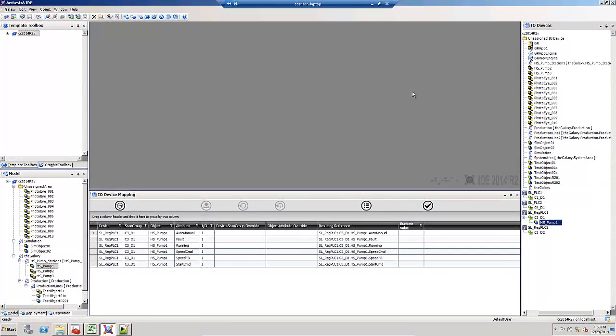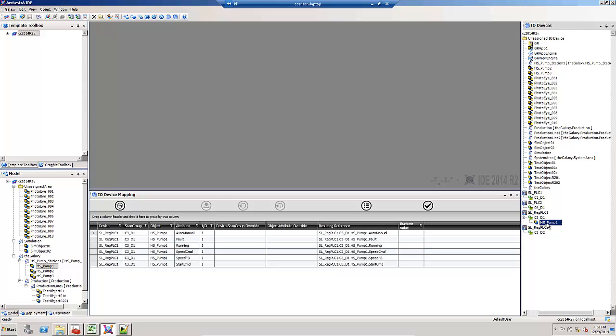So what happens if these aren't assigned properly? Here is an example where I've taken one of the HS pumps and dragged it to the wrong DI object where those UDTs don't exist in that PLC. But I've dragged it there.